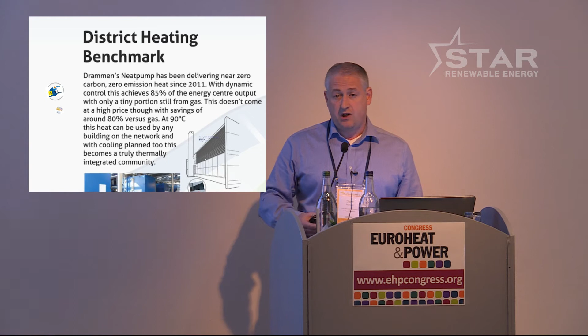It had never been done before, but we did have a history in high pressure working fluids. We did have a history in low charge working fluids and high efficiency. And we were as surprised as a consortium, which was half owned by the city of Drammen and half owned by Fortum, that when we crunched the numbers, an ammonia heat pump used 25% less electricity than an HFC heat pump. They also had the kind situation where the carbon emissions from leaking working fluids were much lower. It's round about 1% per annum from a heat pump, which is round about 800,000 kilometres of driving equivalent, had this been R134A. So that was a massive piece for the city.